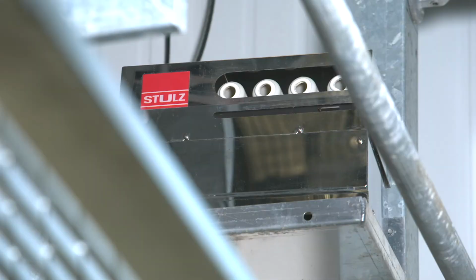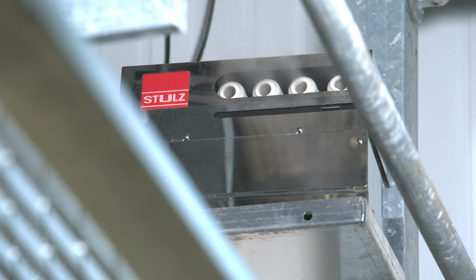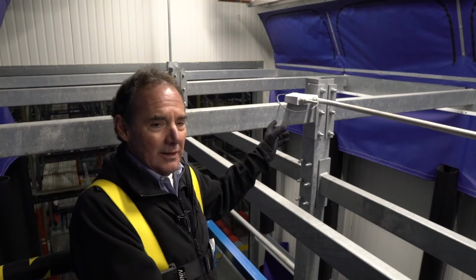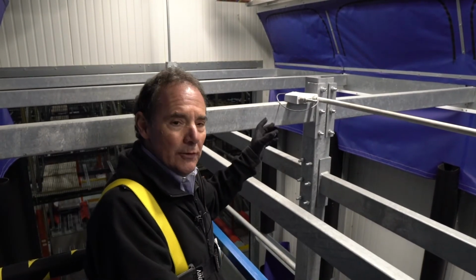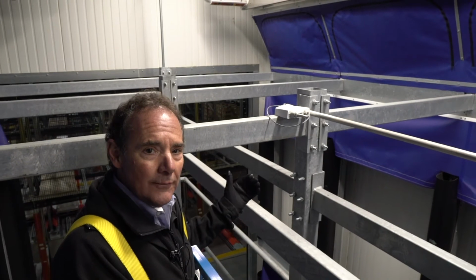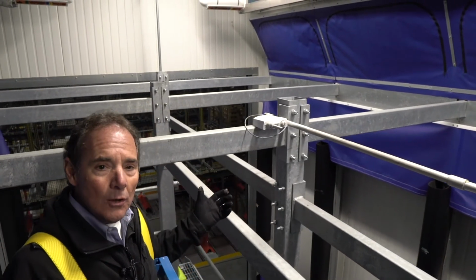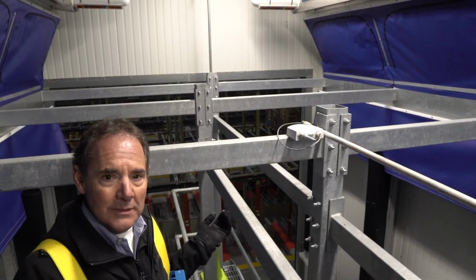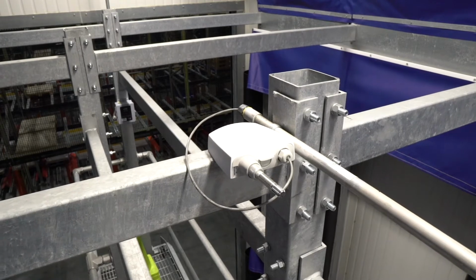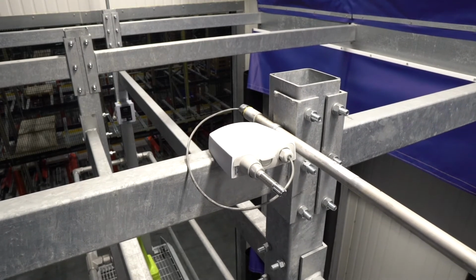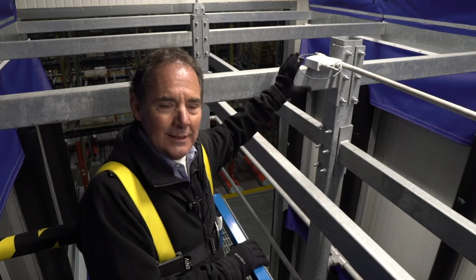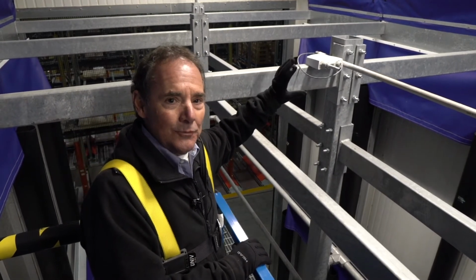The humidifier located in the back of the room is designed to maintain industry recommended 90% relative humidity during the entire ripening cycle. This is the humidity sensor. This is what turns your humidifier on and turns it off during the ripening process based on what you have set at the PLC. One thing that's really important to note is that you must not get the sensor wet. Be sure to cover this sensor with a plastic bag during the cleaning of the room, otherwise you'll damage and destroy the sensor.